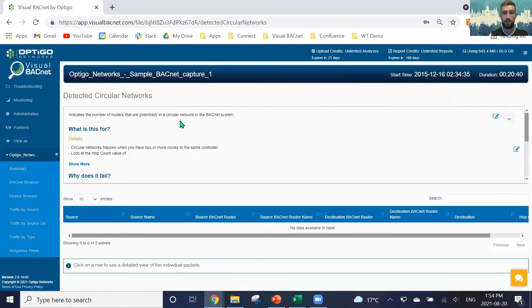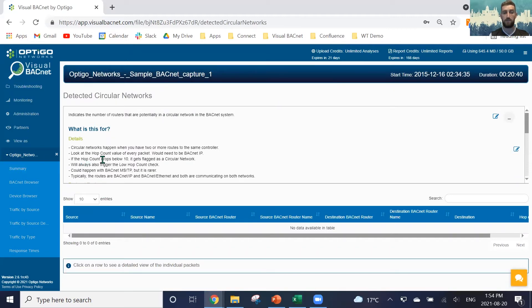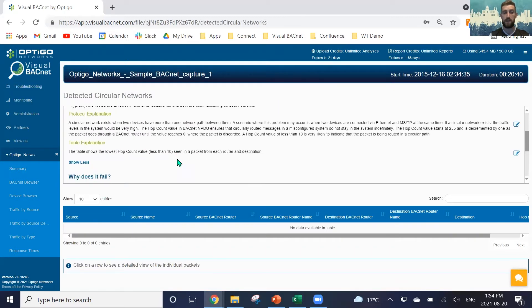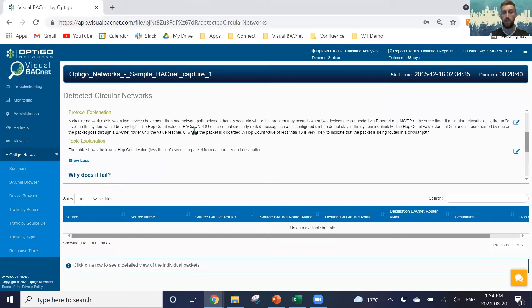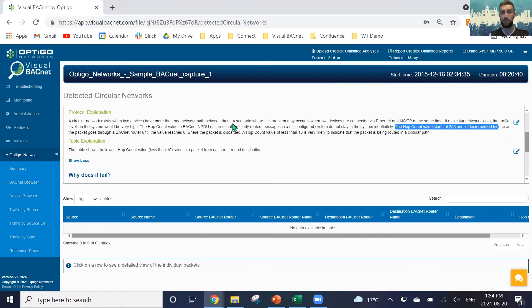Circular networks in this example is a circular network in a system. It occurs when we have the hop count dropping below 10. As we get some more protocol explanation, we see that the hop count starts at 255 and then it's decremented by one as it goes through a BACnet router.